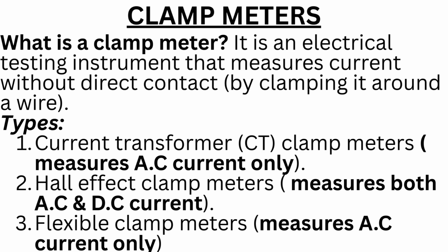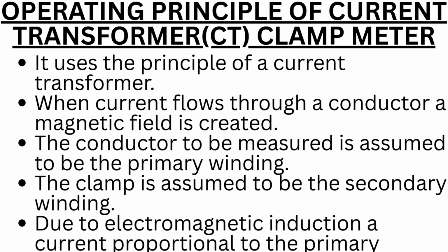Types: current transformer, CT, clamp meters, measures AC current only. Hall effect clamp meters, measures both AC and DC current. Flexible clamp meters, measures AC current only. Now let us look at the operating principle of current transformer clamp meter. It uses the principle of a current transformer.